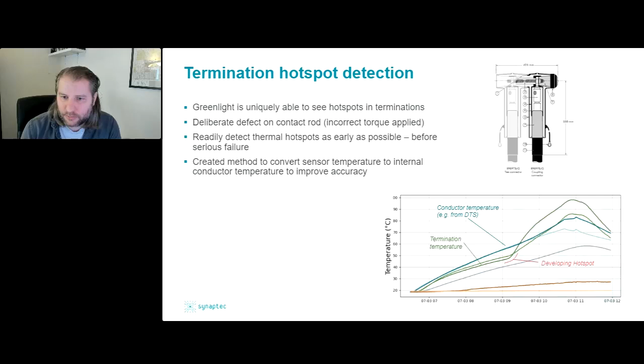As an aside, we've also used the data from this experiment to estimate the conductor's internal temperature, but from externally mounted sensors. So we've developed a transform for how to do that. This gives us the best of both worlds, particularly when looking at the rate of change of temperature and trying to judge if something critical has gone wrong in the cable or the termination. We get accurate point sensing at critical locations, and we can also infer the actual conductor thermal state internally.